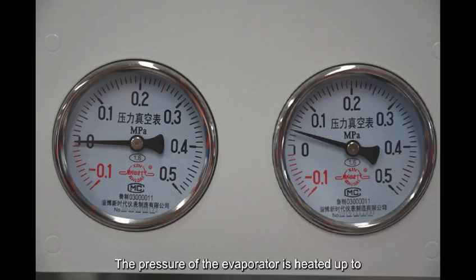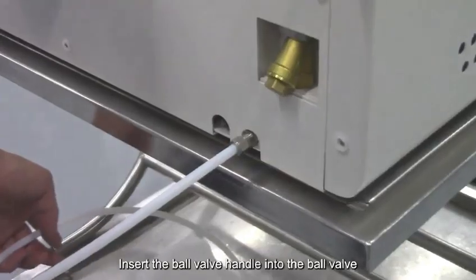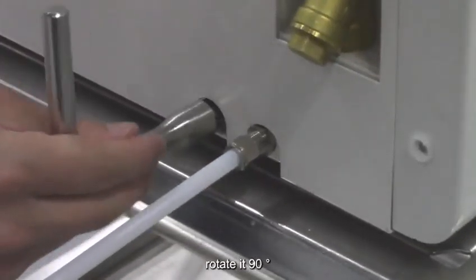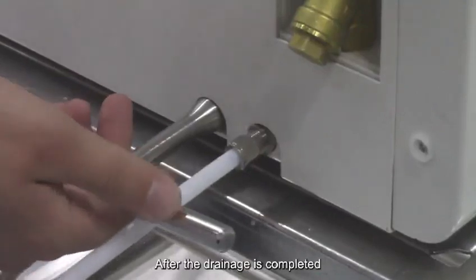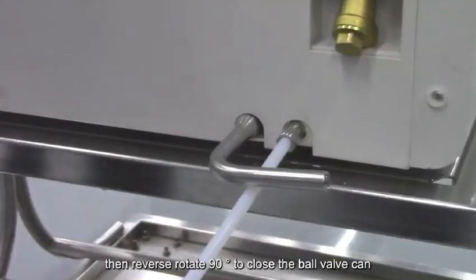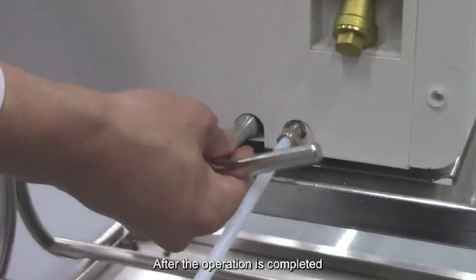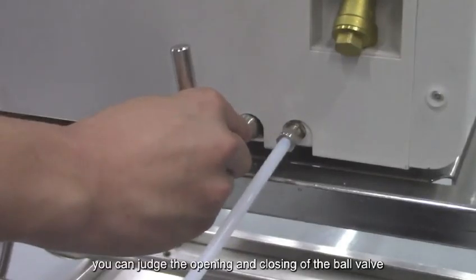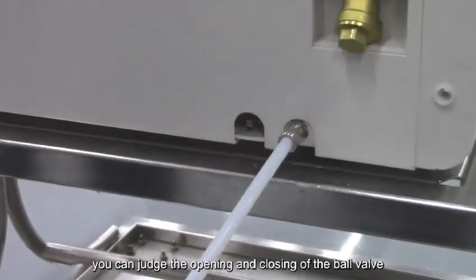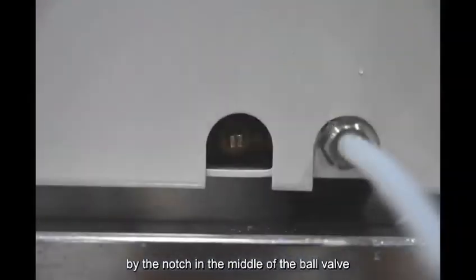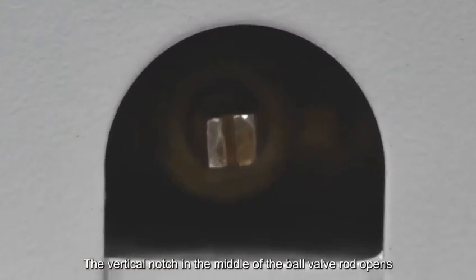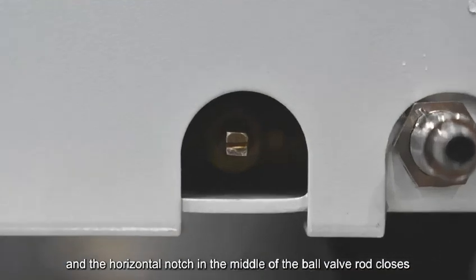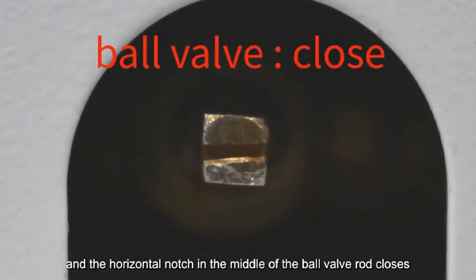The pressure of the evaporator is heated up to about 30 kPa to 50 kPa, conducive to drainage. Insert the ball valve handle into the ball valve, rotate it 90 degrees, and after the drainage is completed, rotate it back 90 degrees to close the ball valve. After the operation is completed, you can judge the opening and closing of the ball valve by the notch in the middle of the ball valve. The vertical notch in the middle of the ball valve rod means open, and the horizontal notch means closed.